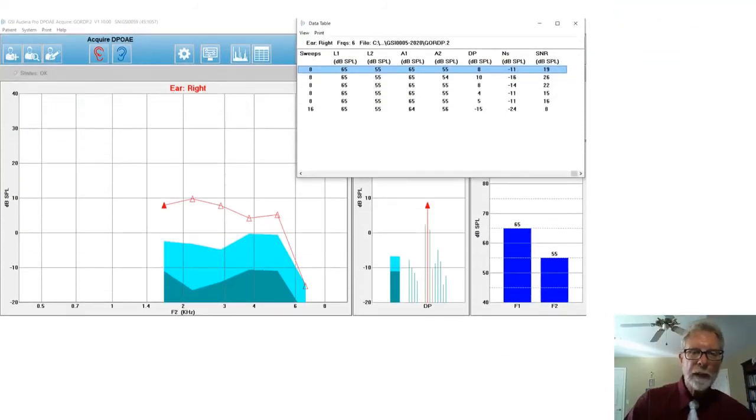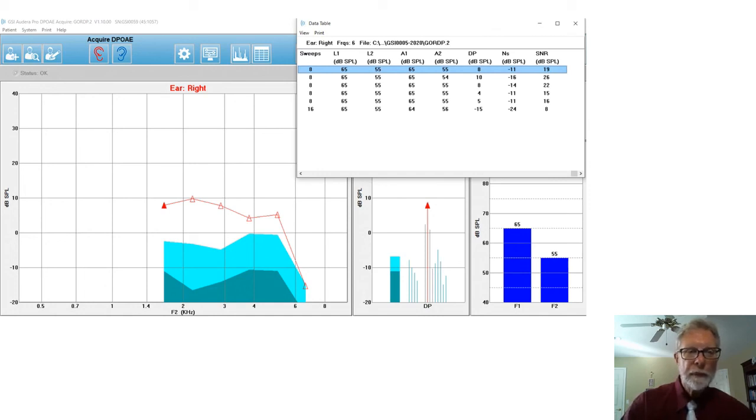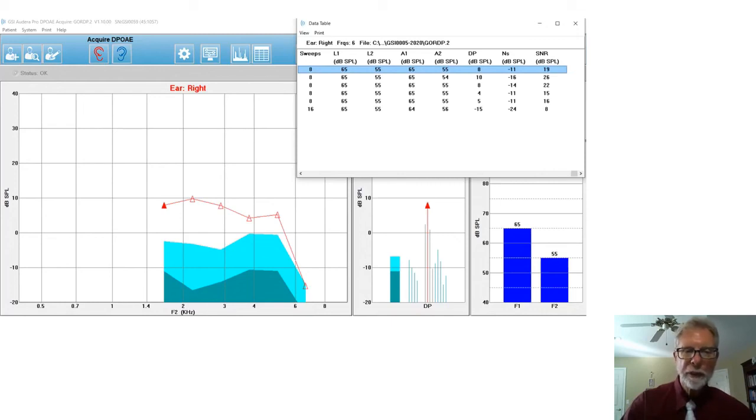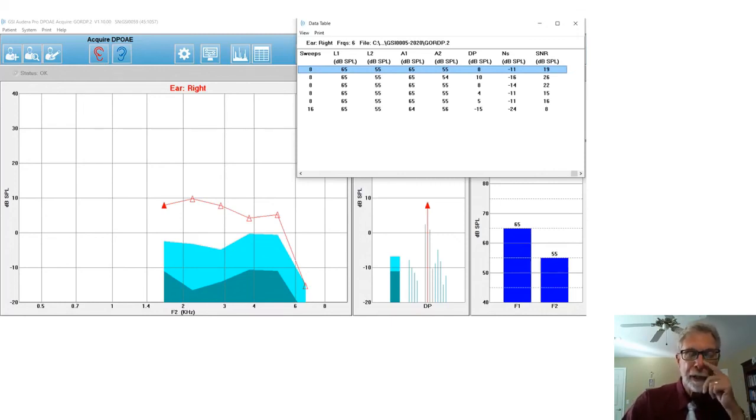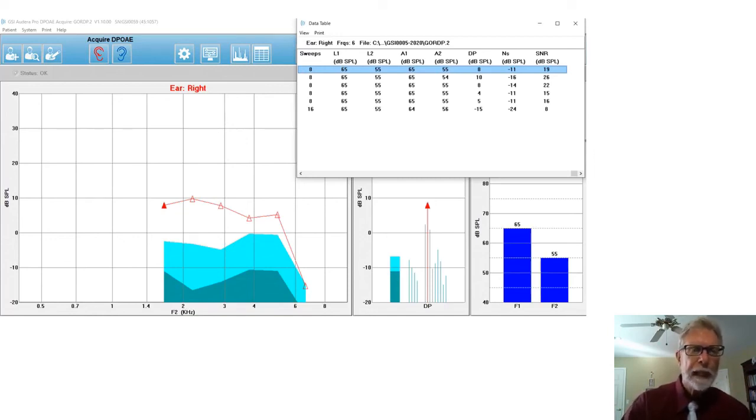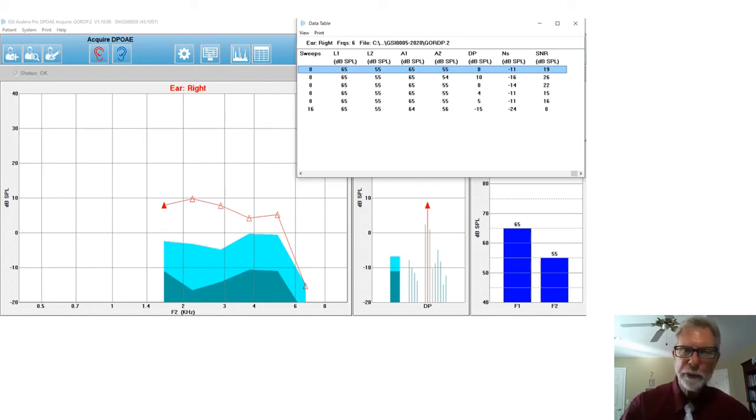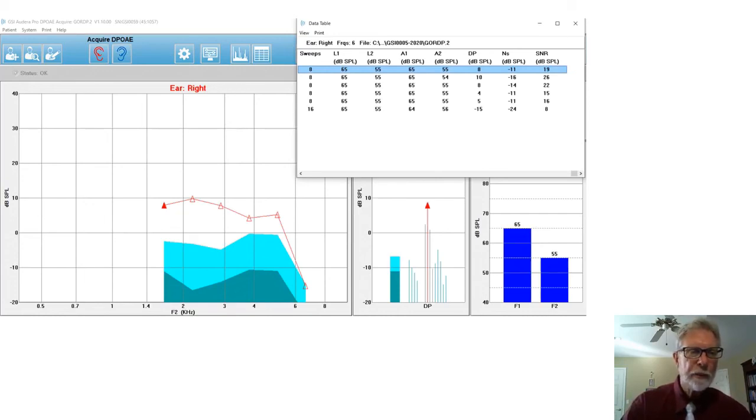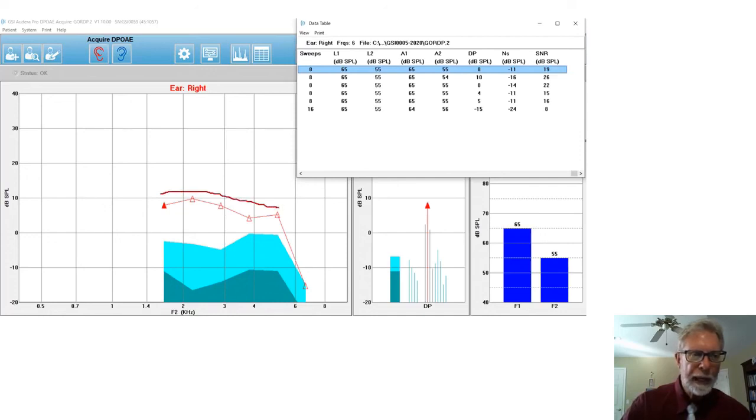Here's a typical popular DP-OAE test that I just ran on myself. It's very typical because I have a lot of customers who use this all the time, just six frequencies, six frequencies in between, say, 1500 and 6000. And it runs it fast. It has excellent filtering in it. And as you can see, here are my OAE levels. And this area is the noise level down here.